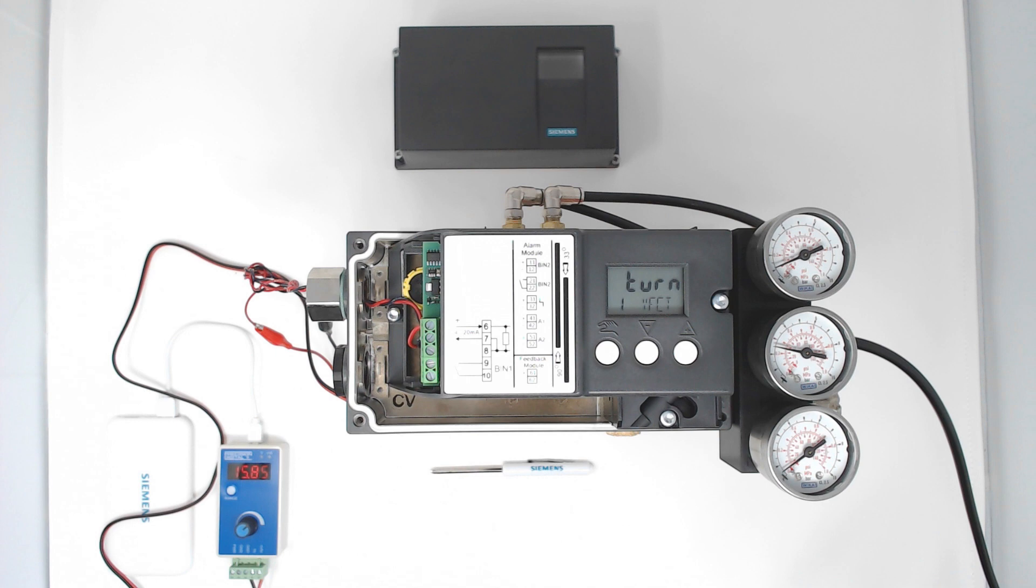Also utilize these indicators as your maintenance program to alert you to which valves need attention rather than servicing valves that perhaps don't have any issues. These diagnostic alarms like number of valve strokes and changes of direction can alert you when it exceeds your mechanics thresholds of O-rings, for example, in your actuator.